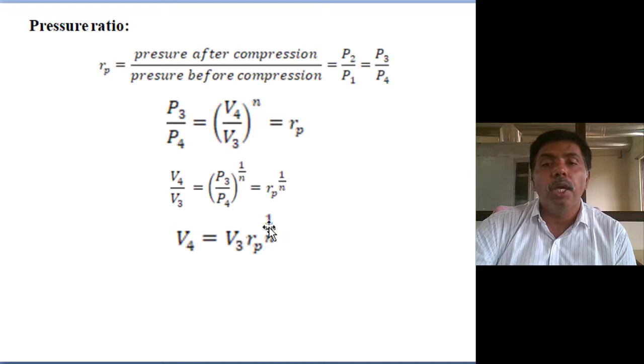Then volumetric efficiency equals effective suction volume V1 minus V4 by swept volume V1 minus V3. Substituting the V1 value, V3 into 1 by C plus 1 minus V4, where V4 is V3 into Rp power 1 by n, divided by V3 into 1 by C plus 1 minus V3. V3 cancels. The final expression is 1 by C plus 1 minus P2 by P1 whole power 1 by n, divided by 1 by C plus 1 minus 1, which is 1 by C. Bringing 1 by C to the numerator gives C, and multiplying C inside, C cancels: 1 plus C minus C into P2 by P1 whole power 1 by n.